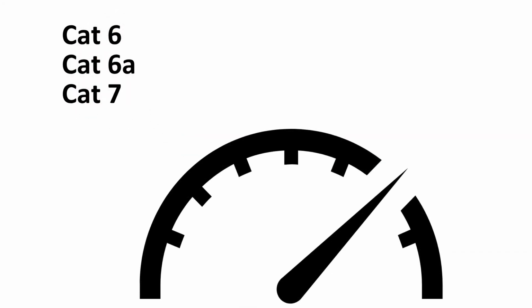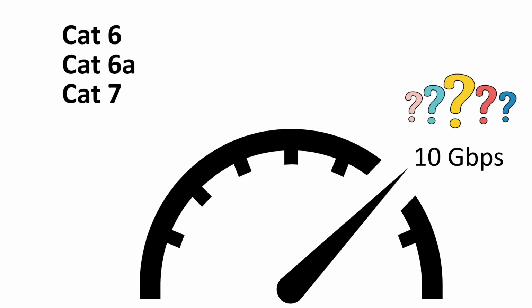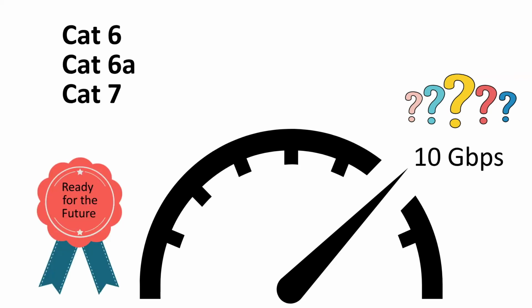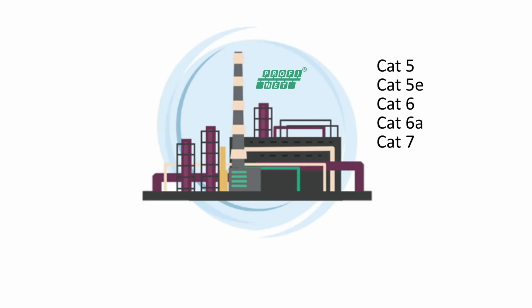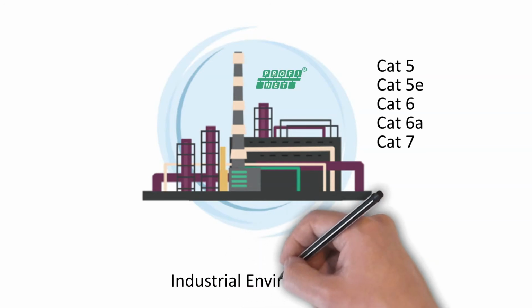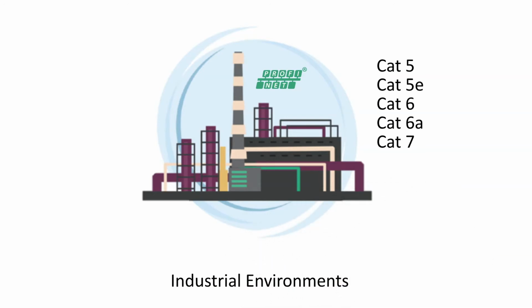Cat6, 6A, and Cat7 cables can provide transmission speeds of up to 10 gigabit per second. Such high rates might seem unnecessary based on current hardware transmission and speed capabilities, but some users choose them to future-proof their network. Profinet networks can employ all of these, but the categories alone don't address their use in industrial environments. The cabling you choose should also therefore meet the Profinet specification.